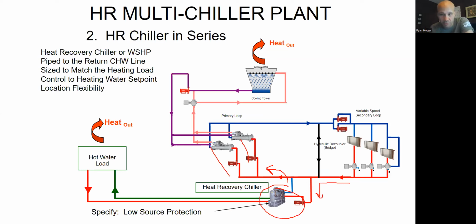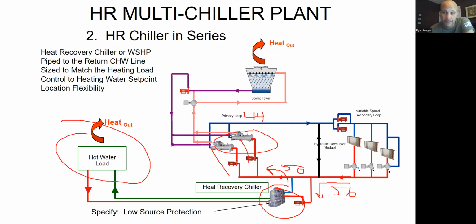So I've got whatever temperature water coming back, right? Say 56 degrees. And this guy's job is to get me down to, let's say, 50-degree water. Then these guys start with 50-degree water and take me down to 44-degree water. So what happens on these guys is they have lower lift because they don't ever see the 56. They only see the 50. So they're going to be running more efficiently than they would in a regular project. So I've made these two more efficient by this guy doing some of their work from up at the front. And I've taken the heat from this water loop and I've sent it over to whoever wants hot water in my building, right?